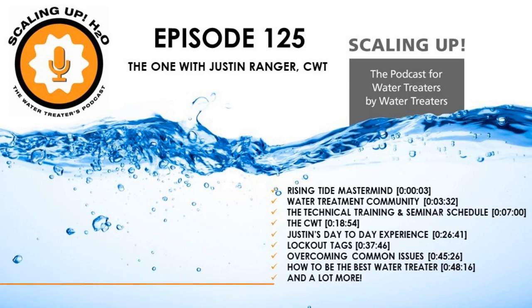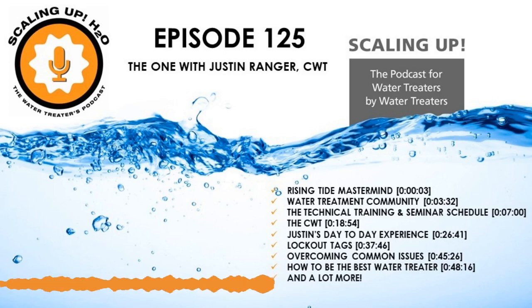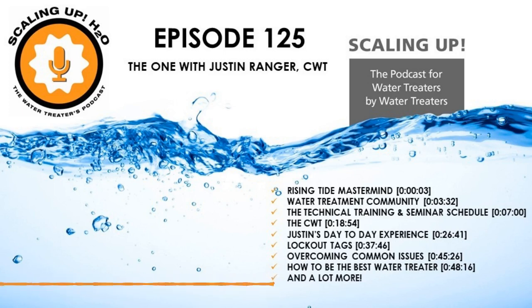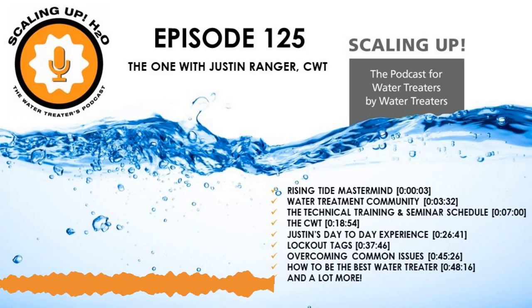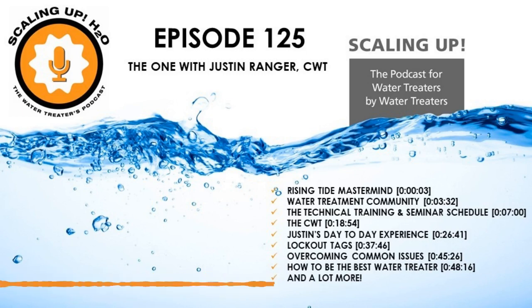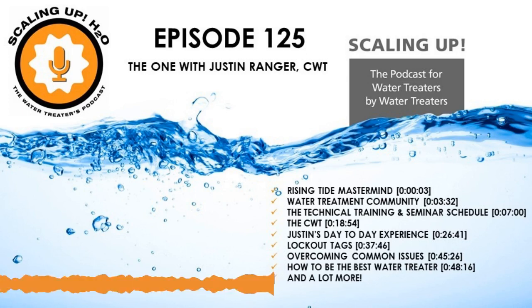With regard to safety, it's good to know what those standards are as a water treatment professional, so if you walk into a boiler room and see a pressure relief valve with a plug in it, you can sound the alarm and get the appropriate plant personnel to say this is not right, this is dangerous and has the potential to really endanger people's life and limb.